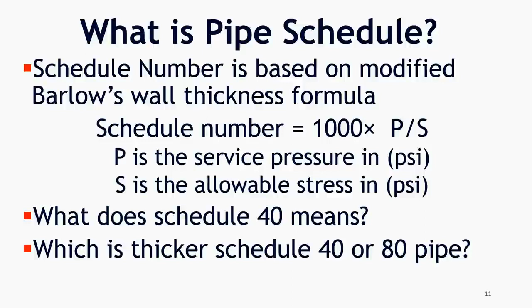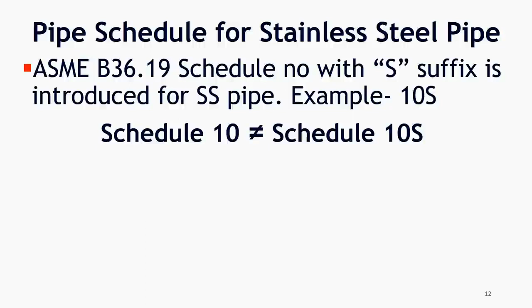Pipe schedule for stainless steel pipe. Cost of stainless steel pipe is much higher than carbon steel pipe. Due to corrosion resistance property of stainless steel, advancement of high alloy stainless steel and fusion welding, less thickness pipe can be worked satisfactorily without fear of early failure. To reduce the cost of material, ASME has introduced different schedule numbers for stainless steel pipe and fittings. Under ASME B36.19, schedule number with S suffix is introduced for SS pipe. Examples are 10S, 20S, 40S and 80S. So keep in mind that Schedule 10 is not same as Schedule 10S. You can see the table for the standard schedule number for carbon steel and stainless steel pipe.